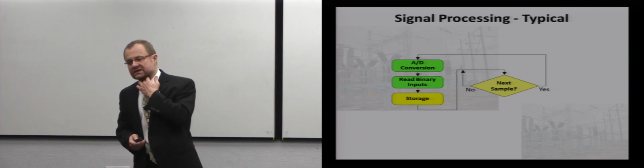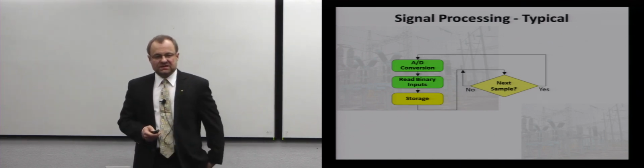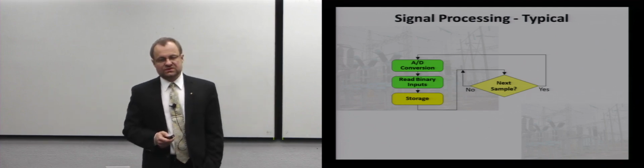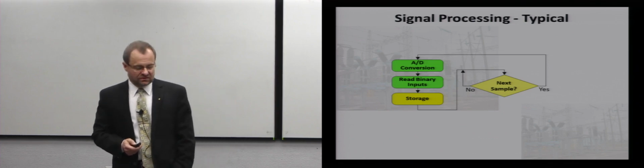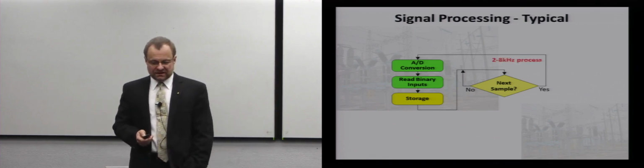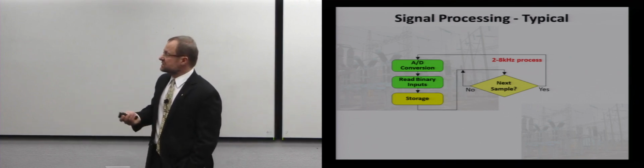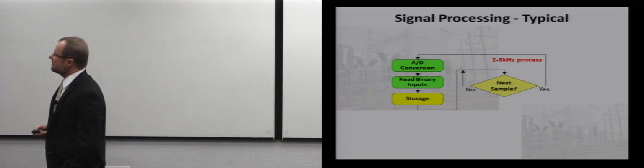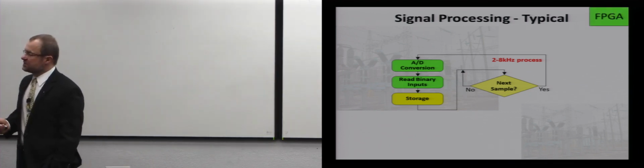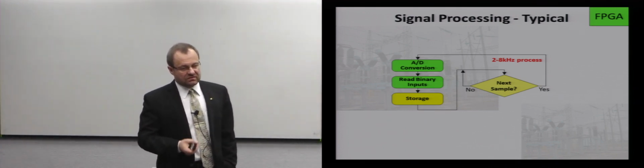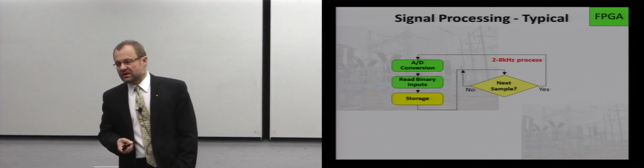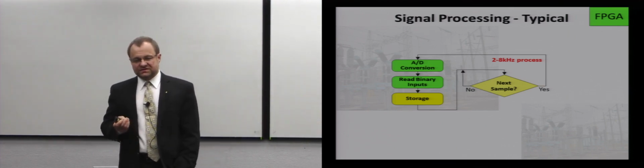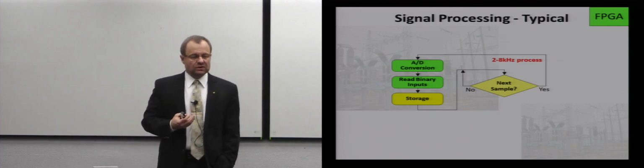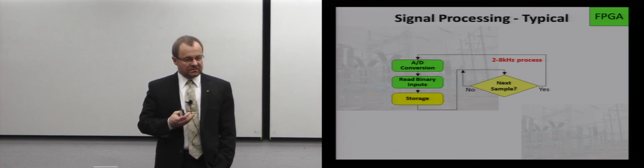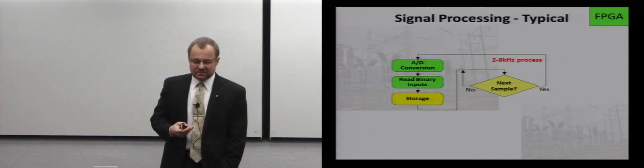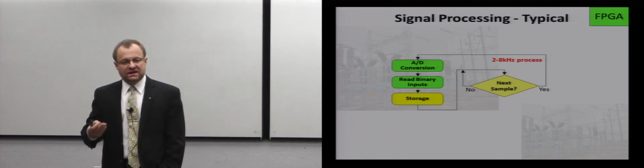Instead, what we do is we break it into typically 3 loops. One loop is basically like a digital fault recorder, meaning that we decided to just get the image of what is going on in our input. So this is just about sampling. I may run it at, say, 2 to 8 kilohertz. New relays could do it, say, at 8 kilohertz. And I will run it in something like an FPGA. What I'm doing really is A to D conversion, reading my inputs, and storing everything in memory. And I may store it for a couple of seconds. So then if somebody comes and says, give me a file that tells me what happened in the power system, I could do this. So this thing is like a recorder, right? Except that the stored data is also available for the real-time protection function.